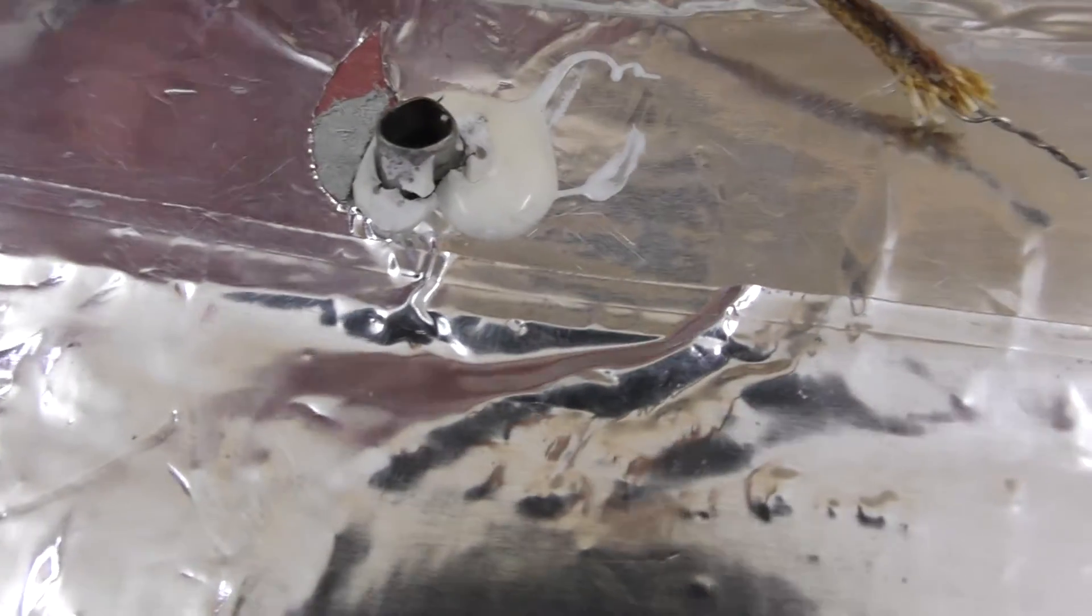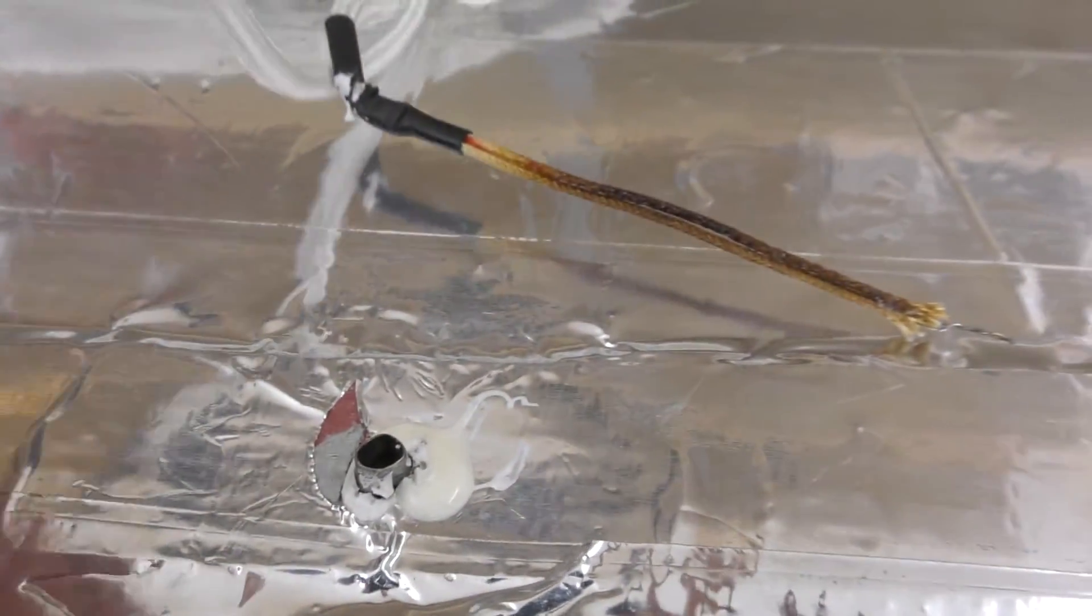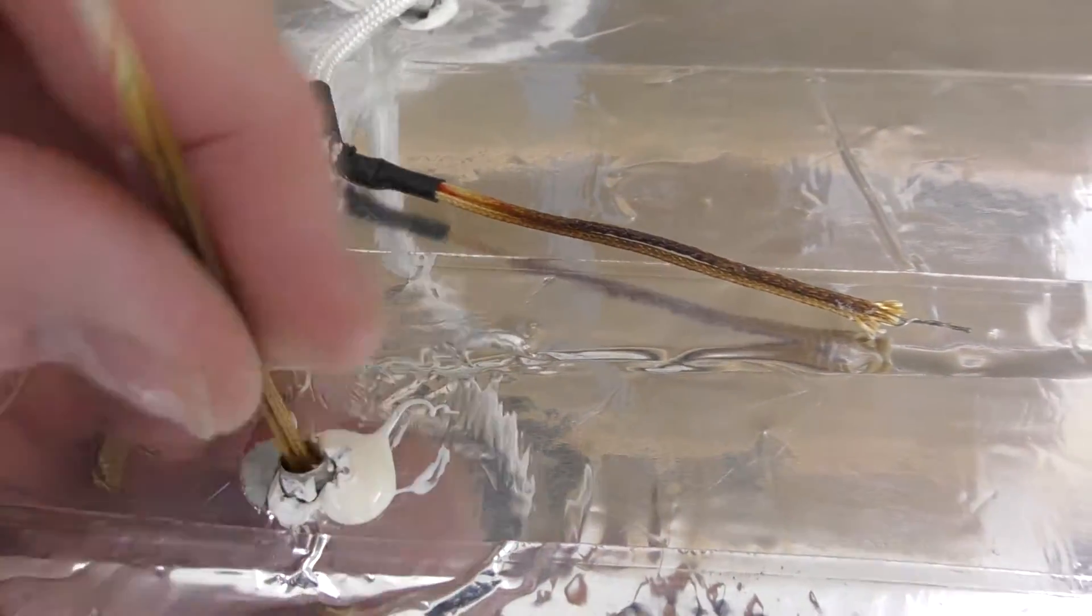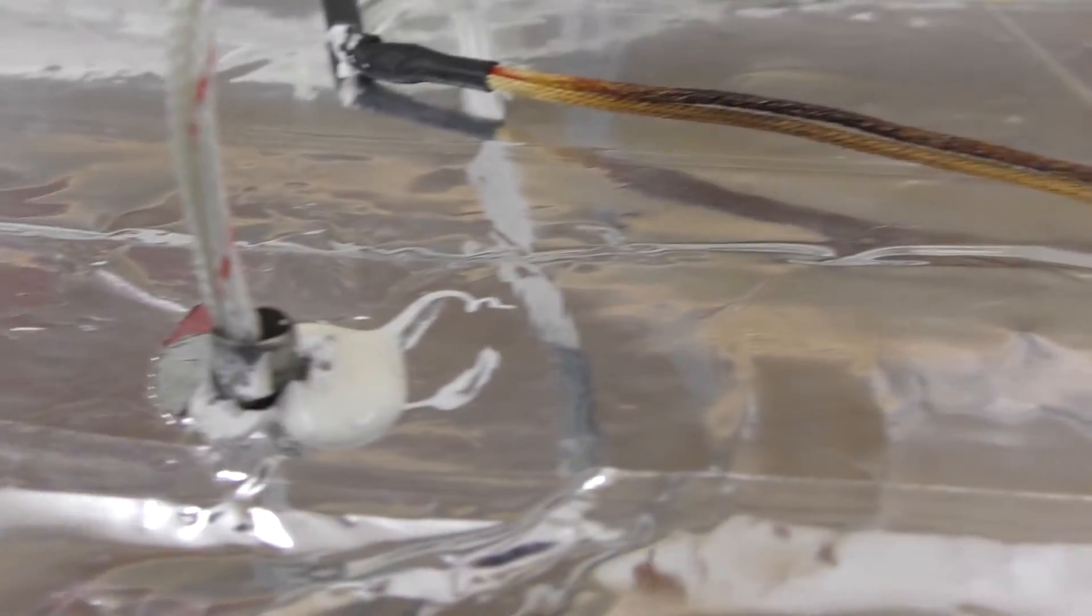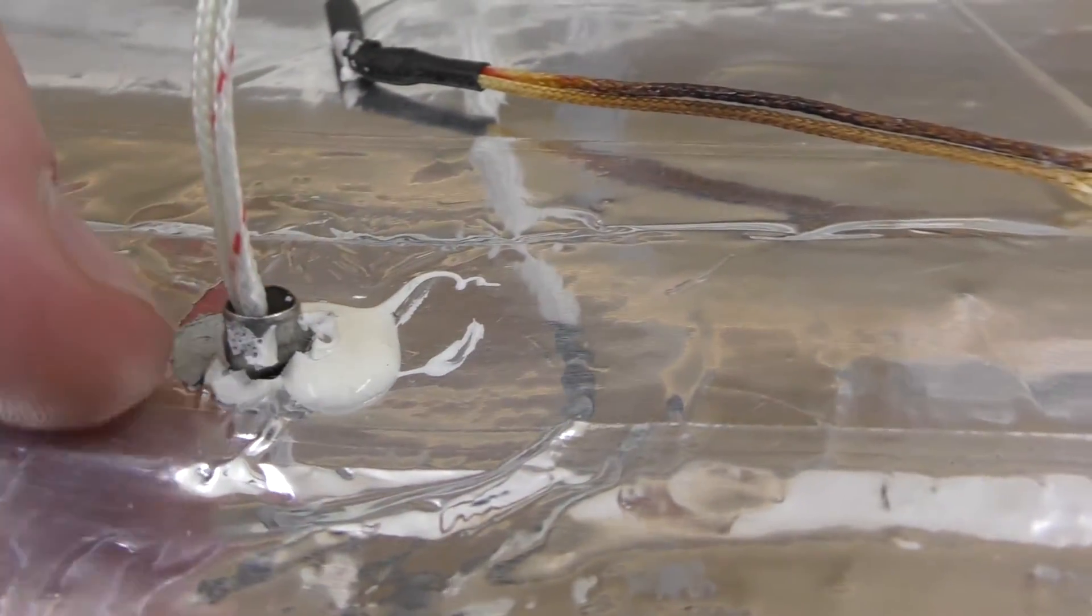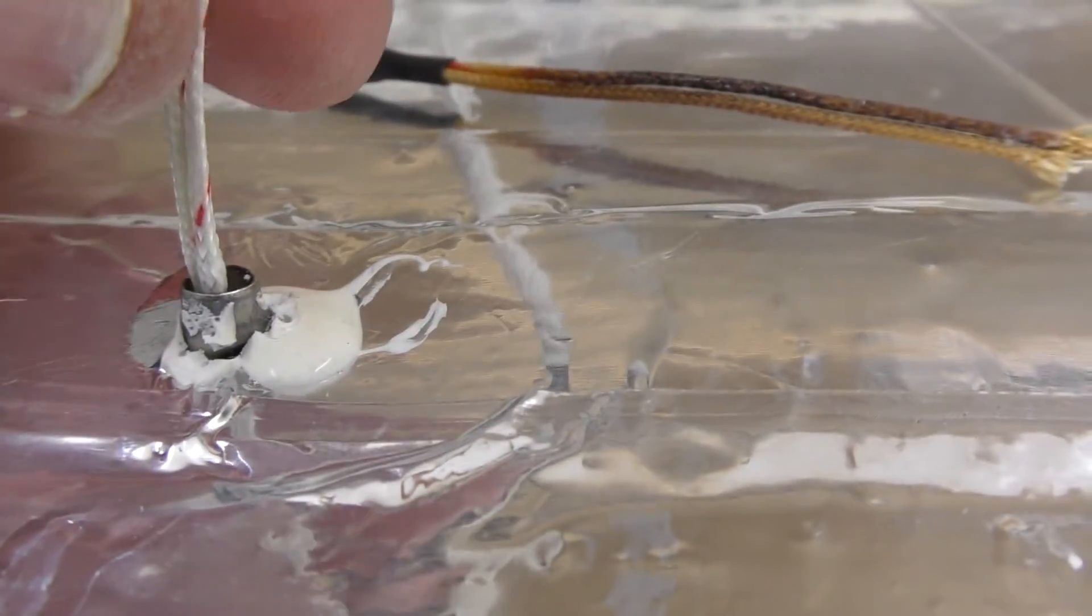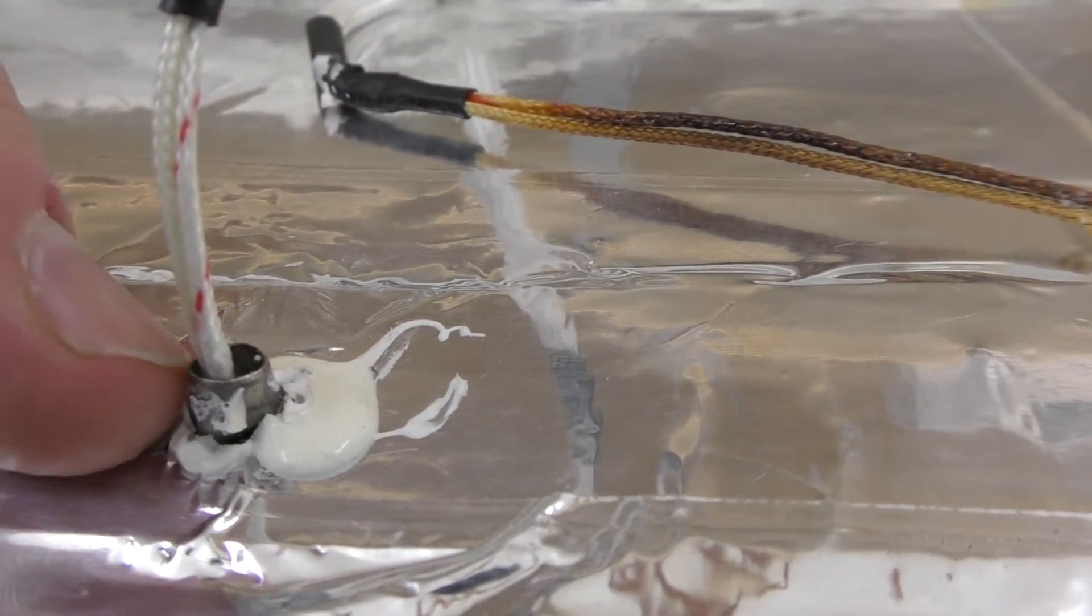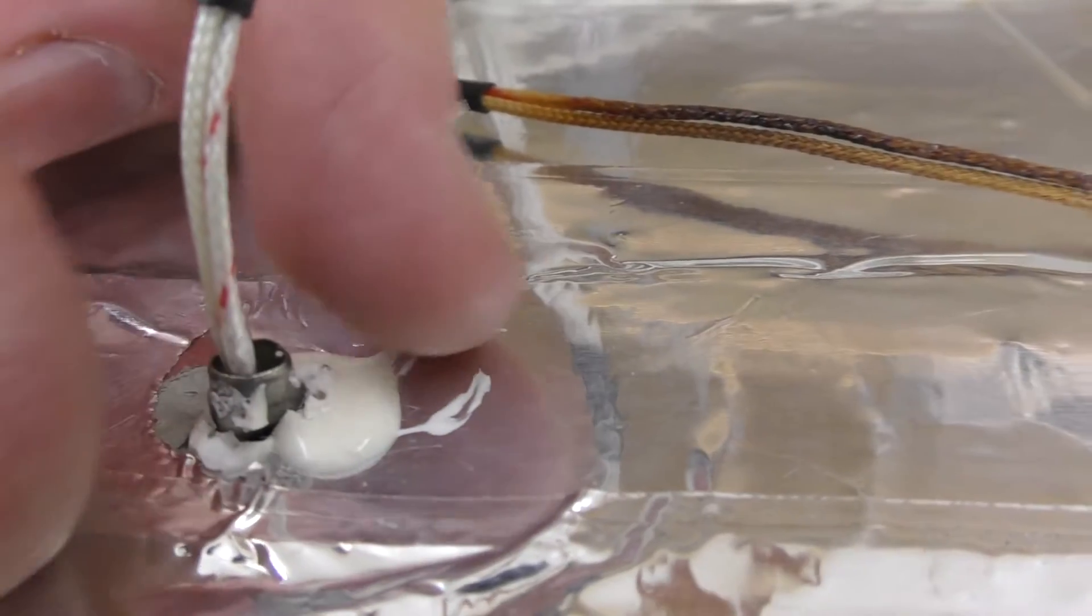Now you'll see here that there is a tube that the thermocouple is passed through. Once the thermocouple is in the right place, that is then crimped slightly at the factory and then some silicon is placed around there. So actually to remove this, you are going to have to squeeze the little metal pipe to open it up again, get the silicon off, and gently tug the thermocouple out.